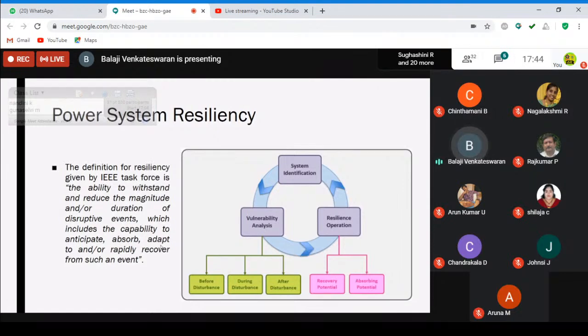When I say vulnerability analysis, I'll give more details in future slides, but we have to understand what are all the main equipment. For example, if we take a substation, or the transformer inside the substation, that is very important. Industry people can understand, if there is shaking of a transformer and it goes beyond 5% of its limit, the bushings will be short-circuited and the transformer may not work. This is in the case of earthquakes.